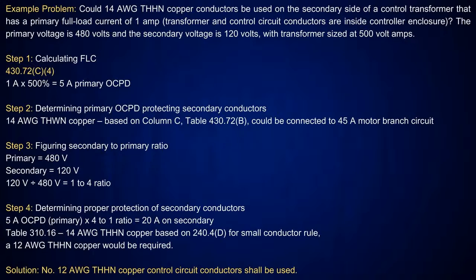Okay, so I'm going to take the 1 amp at 500%, and that's going to give me what? A 5 amp overcurrent device. Okay. And then if I go look at column C in table 430.72(B), it's going to tell me for a 45 amp motor branch circuit here that it could be connected to what? Number 14 conductors. So I'm going to prove this point now. All right. So step 3, I'm going to take the 480 volt primary and divide it into the 120 volt secondary. So that's going to give me a 4-to-1 ratio. Okay. So when I'm determining the proper protection of those secondary conductors, I've got a 5 amp primary times a 4-to-1 ratio here, and that's going to give me 20 amps on the secondary.